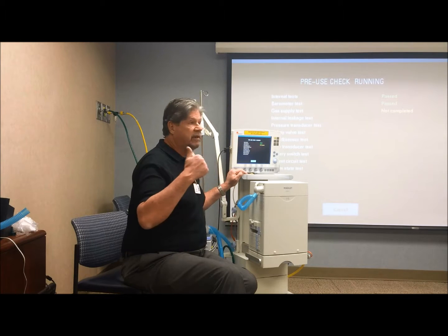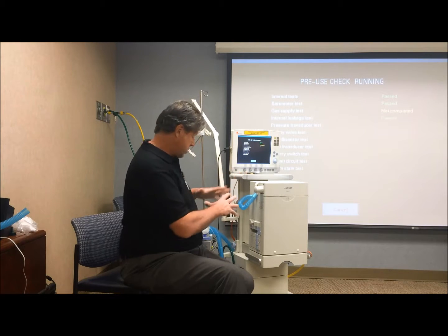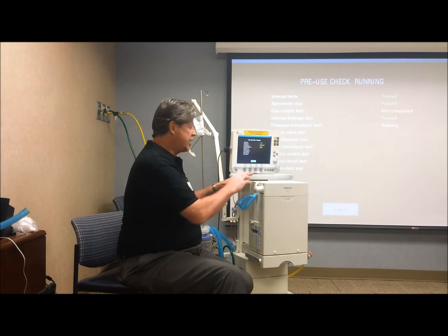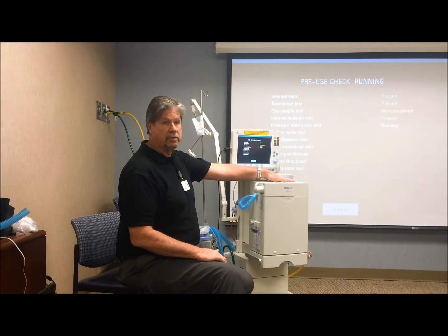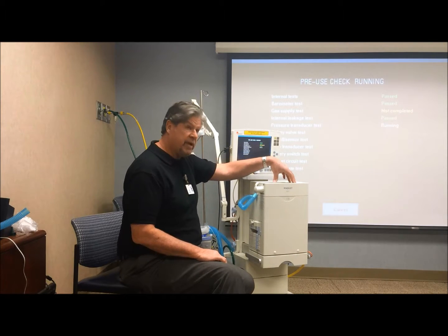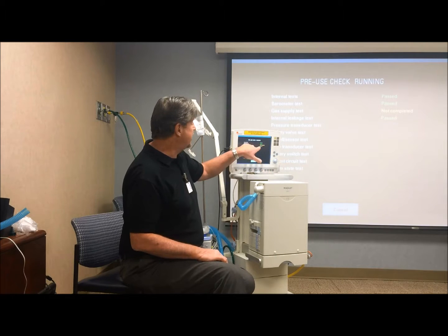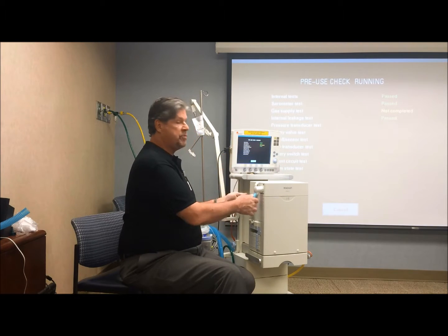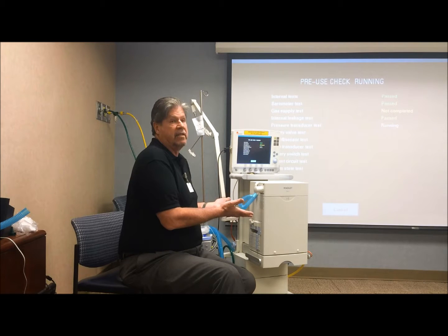So if the internal leakage test fails, there's no circuit on it. It could be the gas modules, O2 and air. It could be the cassette if that internal leakage test failed, or it could be your test lung. Can't be anything else.